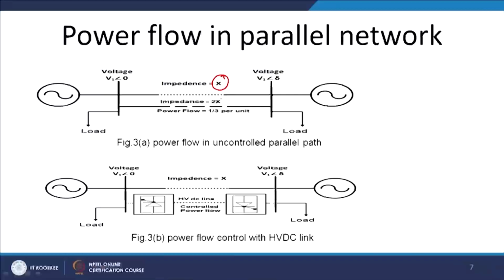Since the upper one has an impedance X and the other has 2X, 2/3 of the power will flow through the upper line and 1/3 of the power will flow through the lower line. But if we try to increase the capability of the lower transmission line, it is sometimes self defeating, because ultimately the power carrying capability will be determined by the impedance of this line. Another solution we can think about, with the uncontrollable line whose power is governed by the impedance of the line, is to put an HVDC link in between.